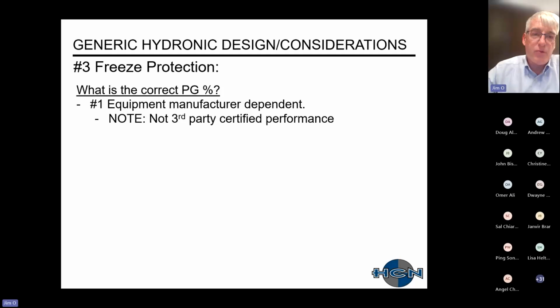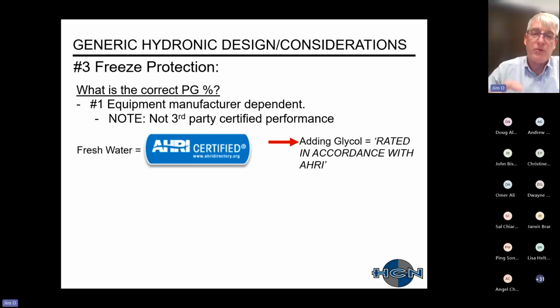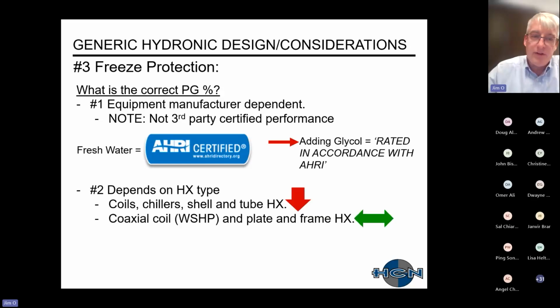Make sure to note there are different glycol manufacturers, and equipment manufacturers also have different glycol derate ratings. I want to point out that once you add glycol to a system, your AHRI certification goes out the window. I don't understand why this hasn't been corrected over the years. If you have a coil with fresh water, you can get an AHRI certified performance. But once you add glycol to it, you get a statement that it's rated in accordance with AHRI, so it's not actually third-party certified.